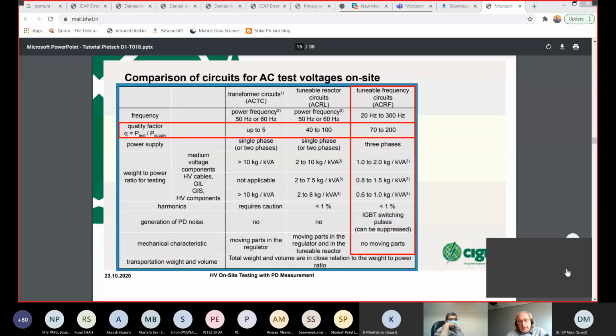As I said, the physical main background for partial discharge is the electrical field and not the voltage. This is always very, very important. Even in a smartphone like this one, you have higher field stresses than in any power equipment you have. Why? Because we have a micrometer scale with 3 or 5 volt. So the electric field is really the main reason. If you can't change anything physically in the transformer, let's say like the shielding of the bushing or whatever, then you have no chance to reduce the PD activity unless you repair or replace some parts. The only thing is to reduce the electrical field, and this is only possible if you reduce the voltage, but this is not normally possible.